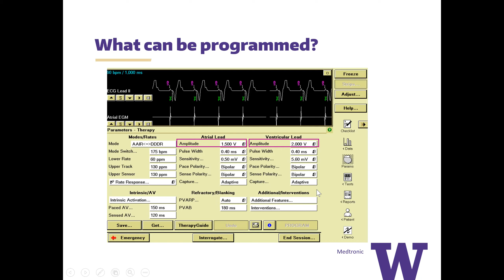The programmer interface shows up like this. I wanted to show you because through this screen you can see that you can program a wide variety of parameters, including the mode, the rates, and the different settings we talked about: the amplitude, the pulse width, the sensitivity, and whether you want it to be unipolar or bipolar. Many parameters can be programmed. The more salient, important ones are probably rate response, which can be on or off. This is modulation of pacing rate in response to input from sensors that measure specific physiological parameters.